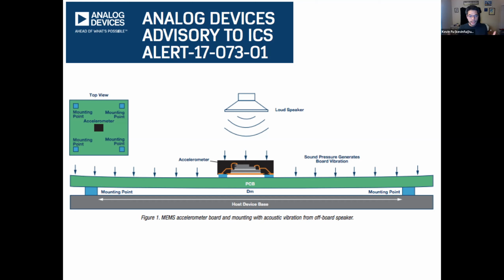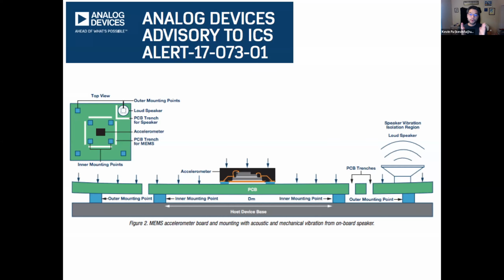In the old, status quo setup, these circuit boards are basically timpani drums, and they will go up and down from the sound pressure waves hitting it. One way to reduce, but not eliminate, the problem is to put the mount points very, very close to the emitters or to the sensors. That causes it to become much more rigid, and it throws a lot of the resonant frequencies closer to the ultrasonic range, which is harder, not impossible, but harder for an adversary to have any appreciable effect.